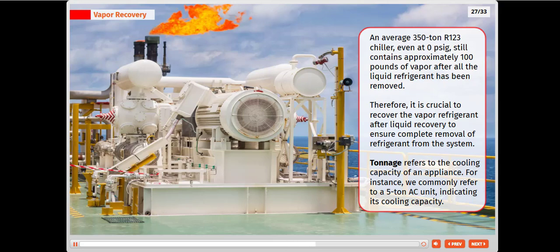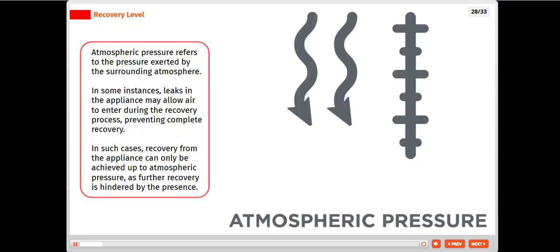Tonnage refers to the cooling capacity of an appliance. For instance, we commonly refer to a 5-ton AC unit, indicating its cooling capacity. Atmospheric pressure refers to the pressure exerted by the surrounding atmosphere. In some instances, leaks in the appliance may allow air to enter during the recovery process, preventing complete recovery. In such cases, recovery from the appliance can only be achieved up to atmospheric pressure, as further recovery is hindered by the presence of air.